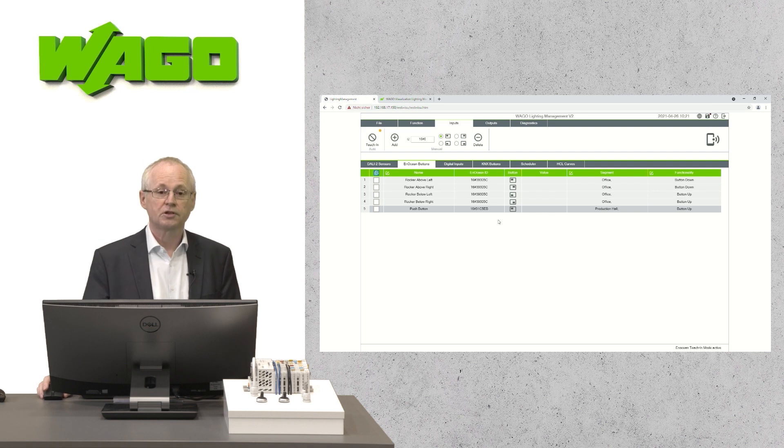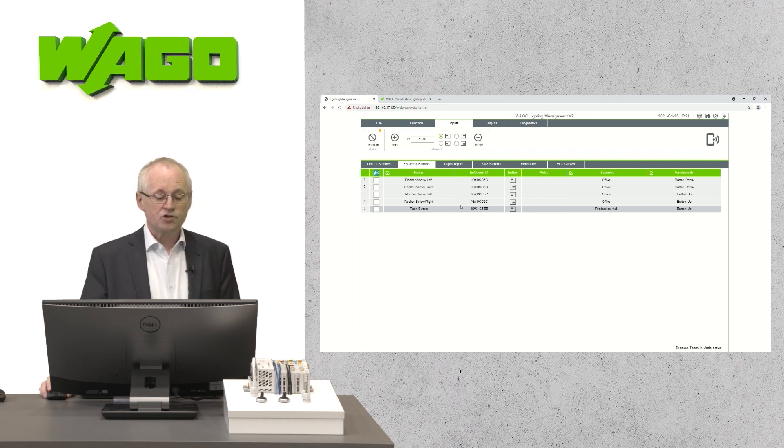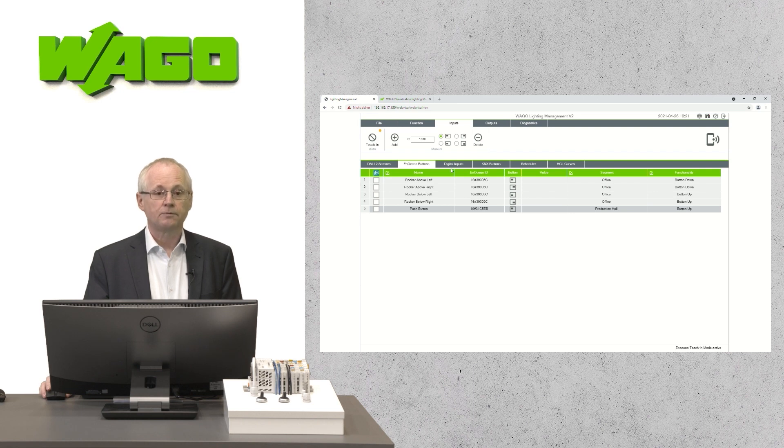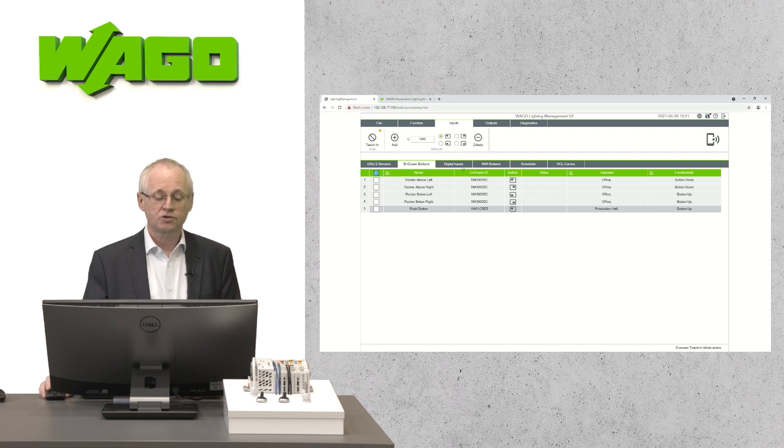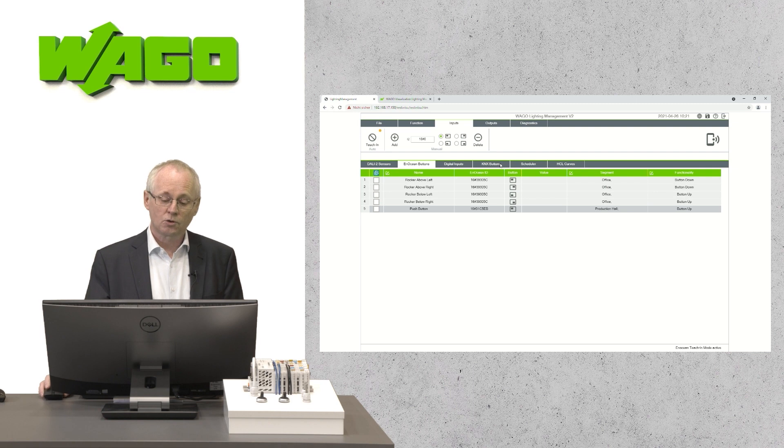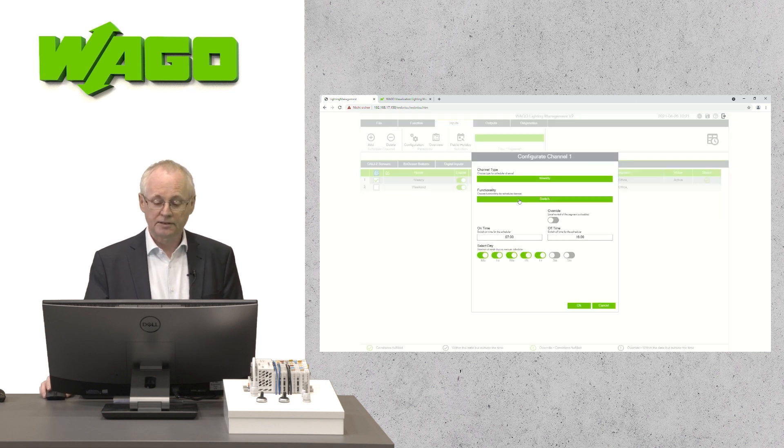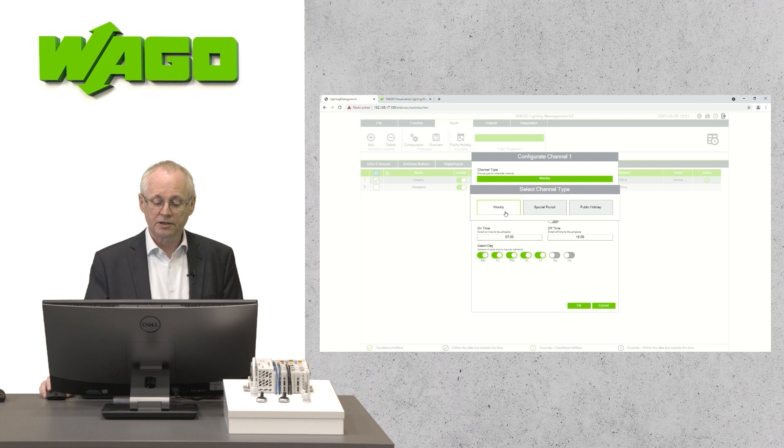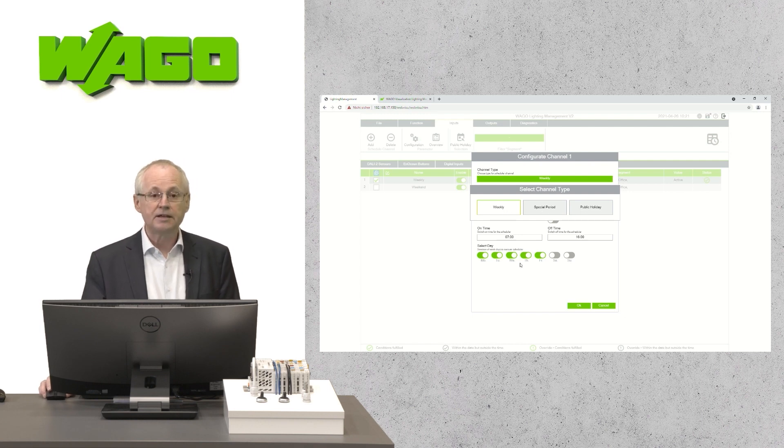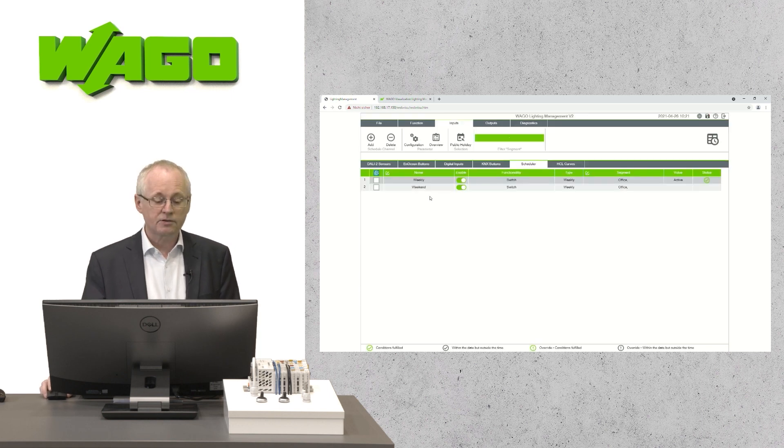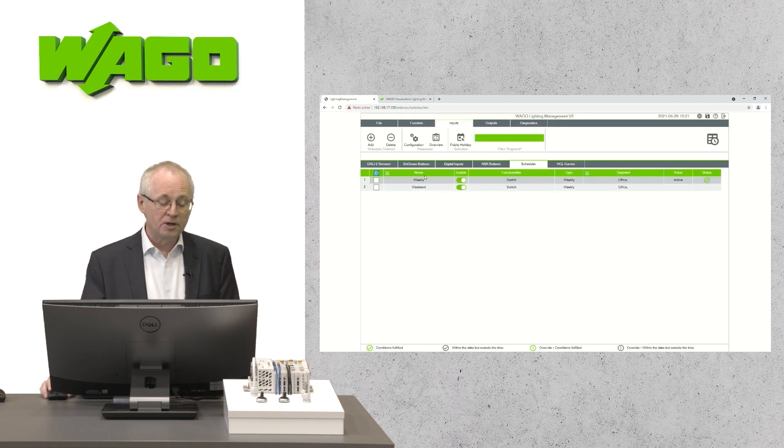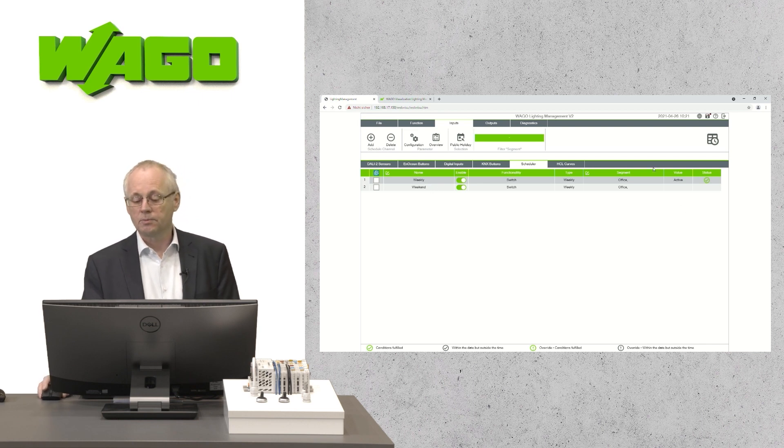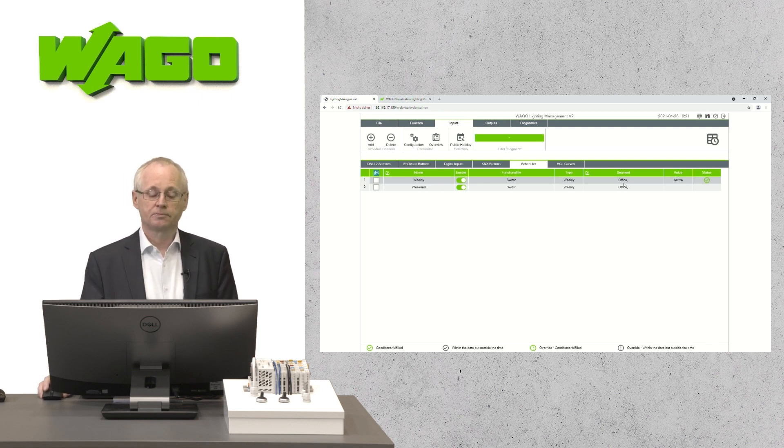With a few mouse clicks, it's done. The application provides also the possibility to connect devices via digital inputs and also via KNX. Also a scheduler is available. You can select between weekly, special days or public holidays. You can select the days and also the switching times. After that, each scheduler can be given a name and the scheduler will be assigned to a segment.